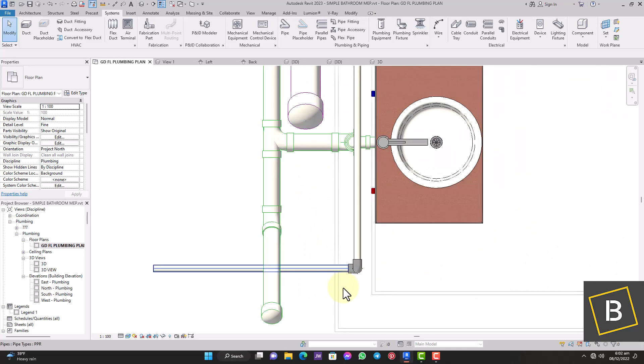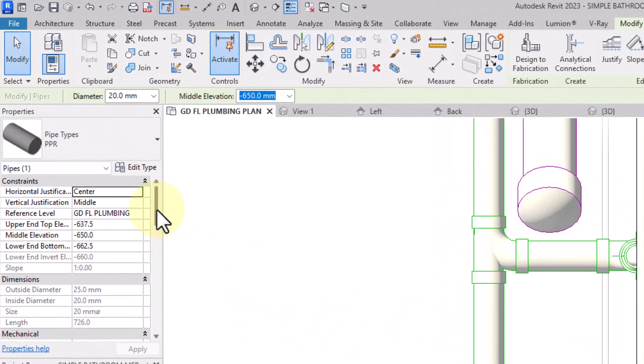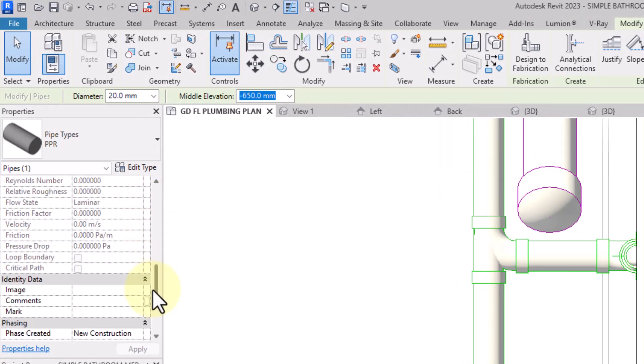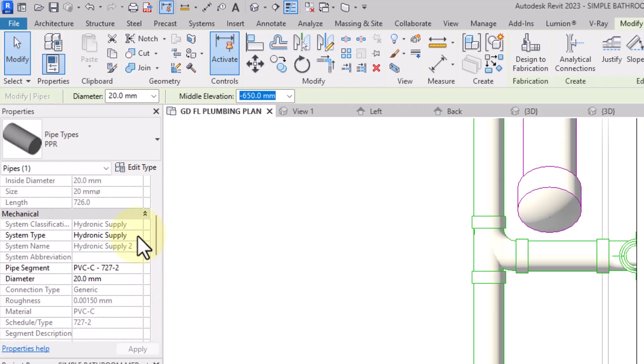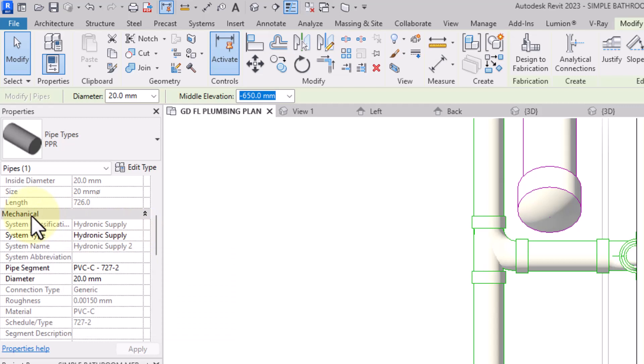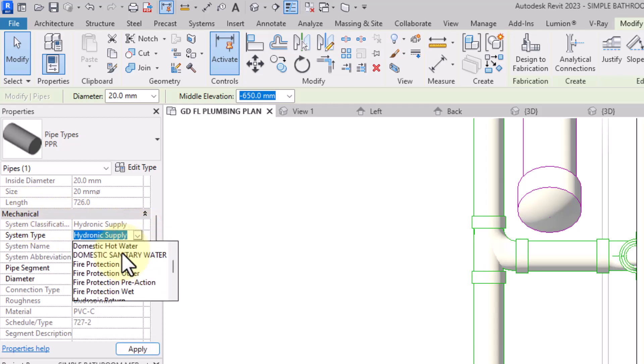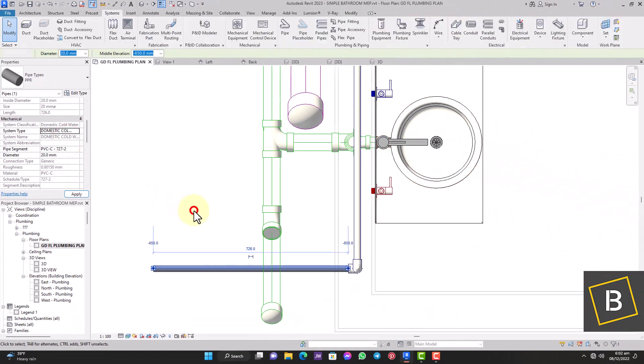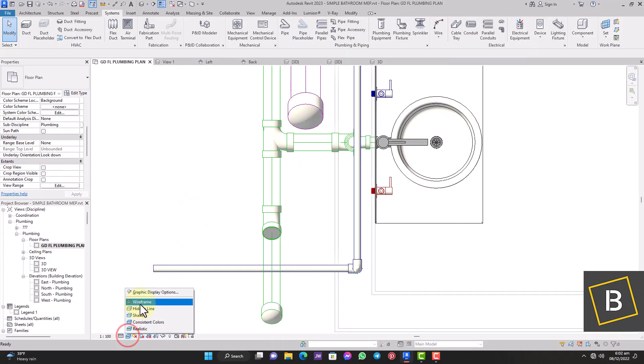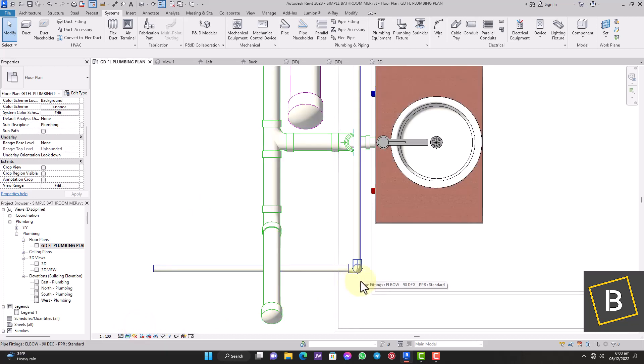You'll notice the pipe appears black, meaning the system classification is incorrect. Move over to Properties and tell Revit that this is a cold water pipe — not a hydronic supply. Under Mechanical System Type, scroll down and select Cold Water or Domestic Cold Water. It may automatically change to blue if you've already done the settings before. If it doesn't change to blue, don't worry — we'll cover that in a later video.